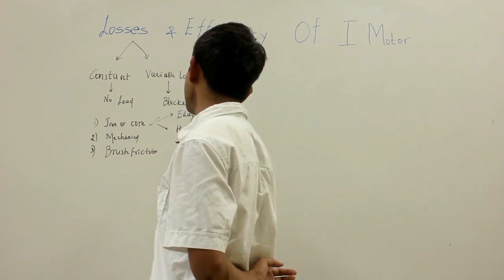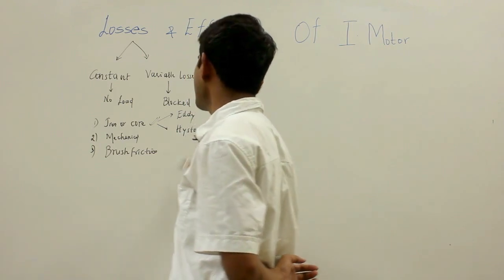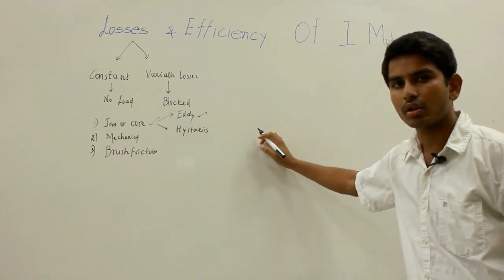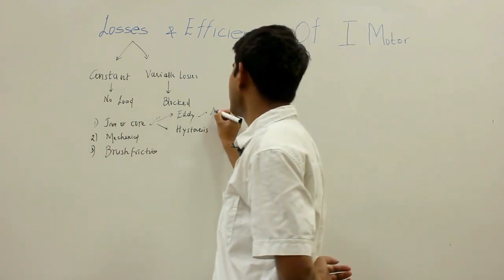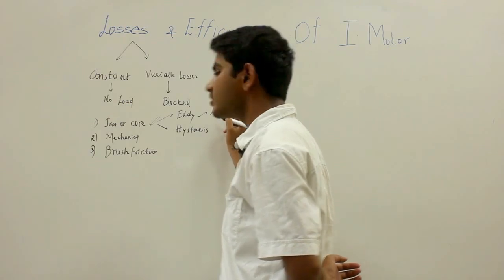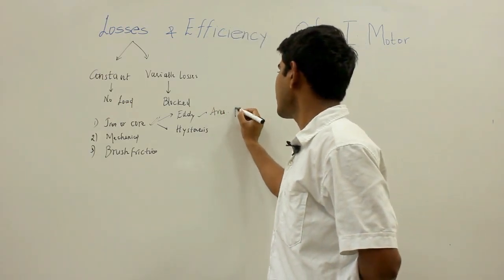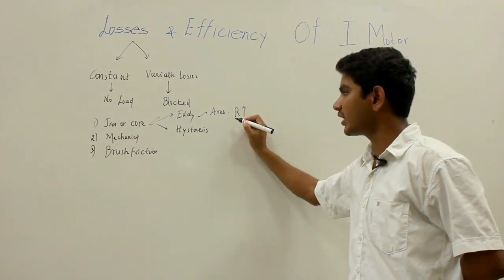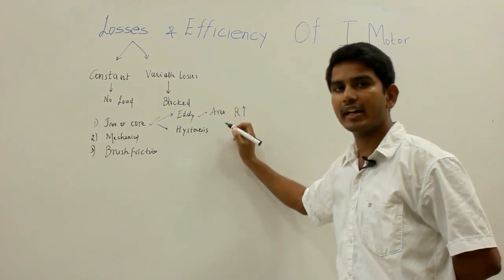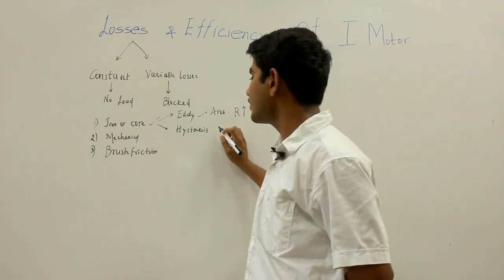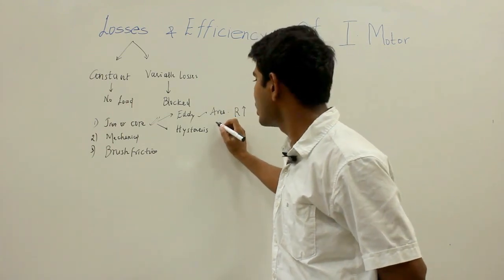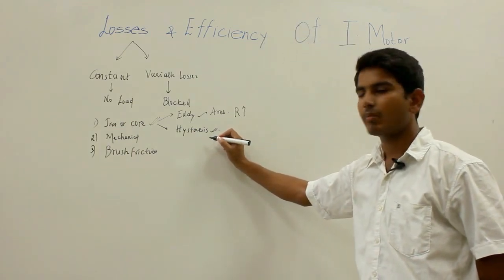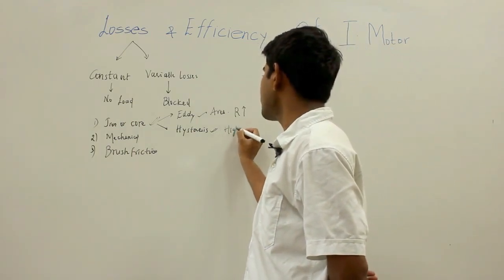Eddy current losses can be minimized by laminating the core. As you laminate the core, you decrease the area of the core. As the core area decreases, the resistance increases, and thereby the eddy current decreases — so eddy current losses can be effectively prevented by laminating the core. Hysteresis losses can be minimized by using high-grade silicon steel.